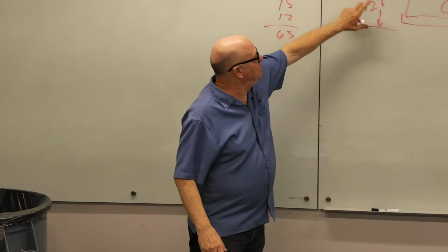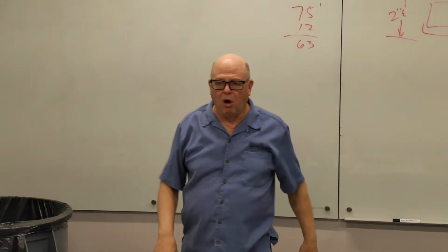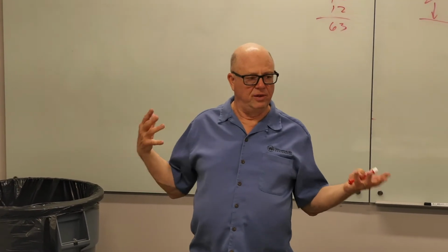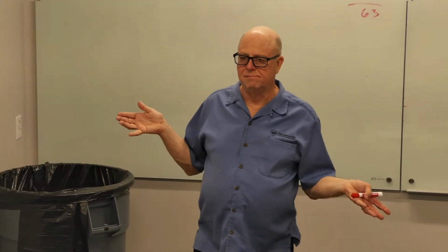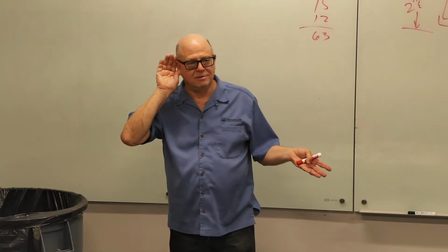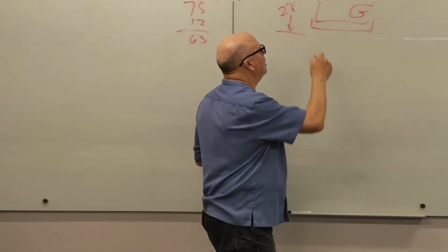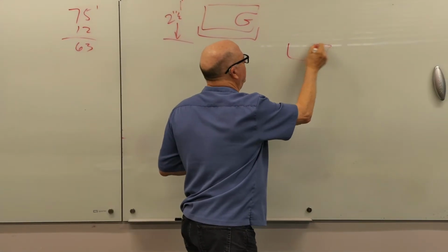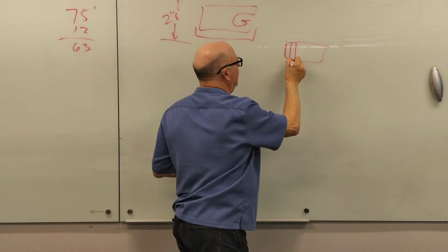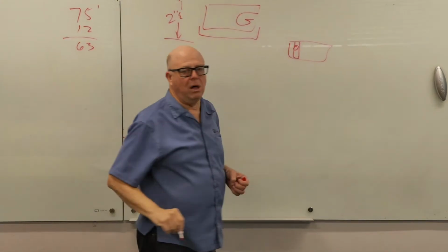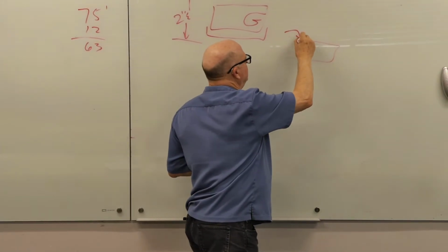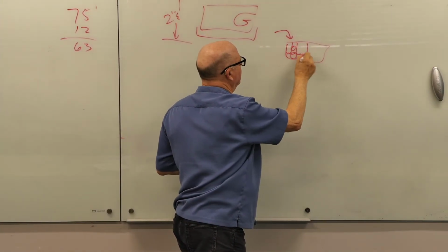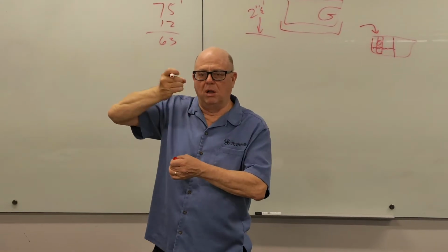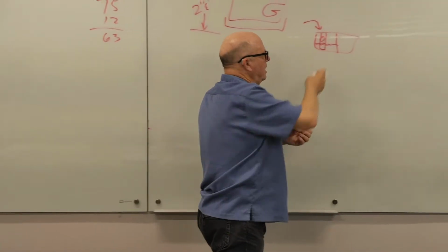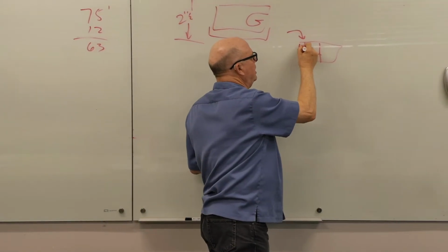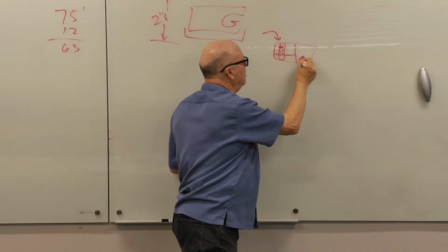And if you've only got this much space and the unit itself is 22 inches tall, how are you going to get the condensate to drain? I heard you say it. Condensate pump? A condensate pump. So condensate pumps are these little devices which I'll greatly oversimplify. They've got a little silo. They've got like a ping pong ball. The water comes into the basin that's got the ping pong ball. When the basin fills up high enough and the ping pong ball goes up high enough, it makes a circuit and the little pump motor pumps out the water.